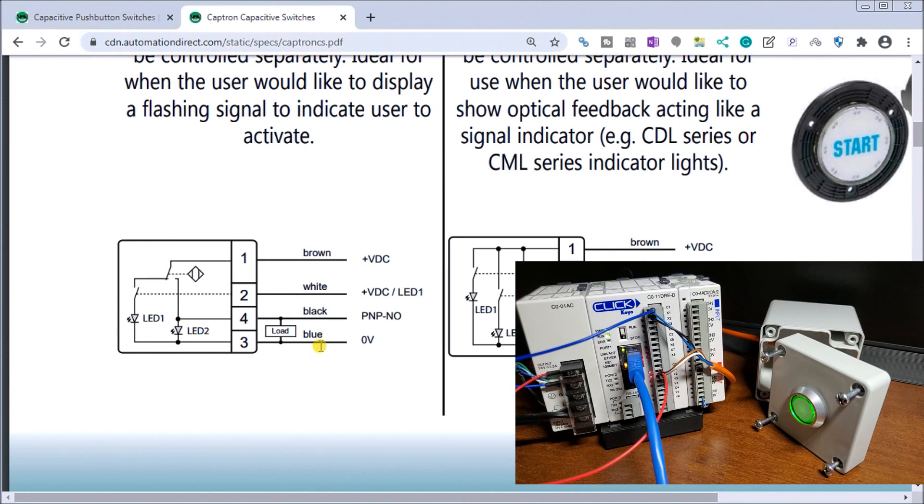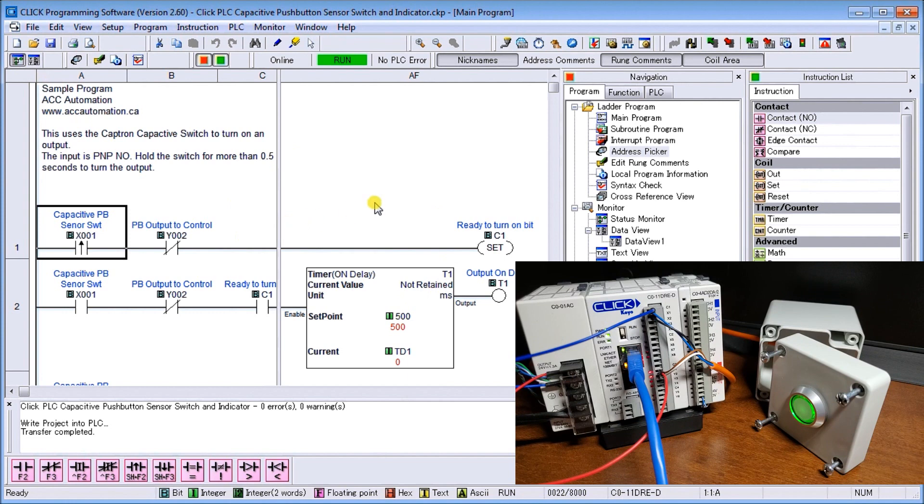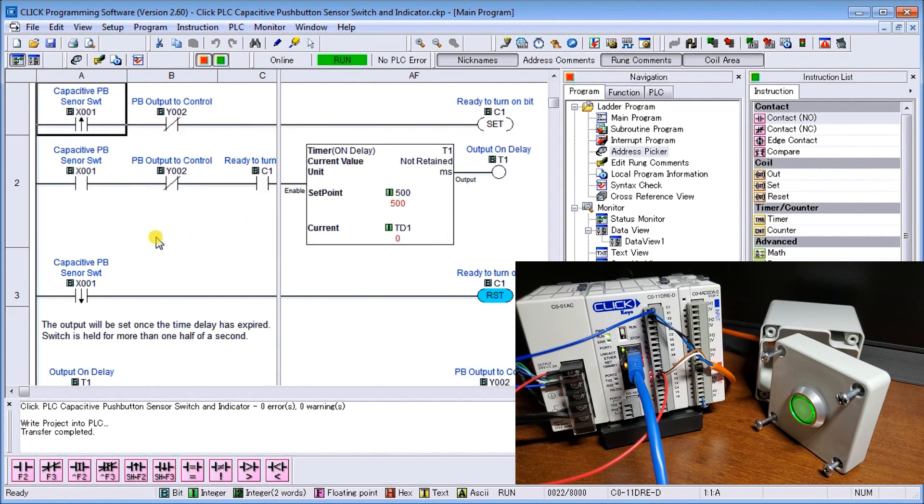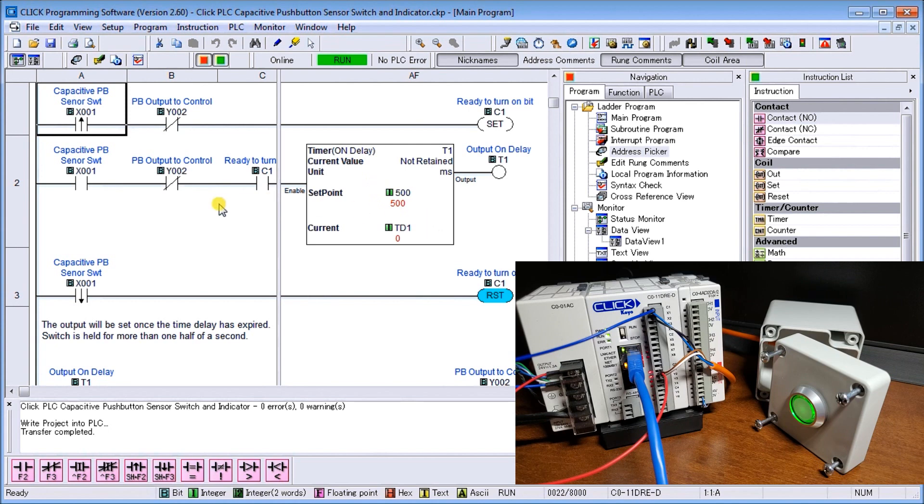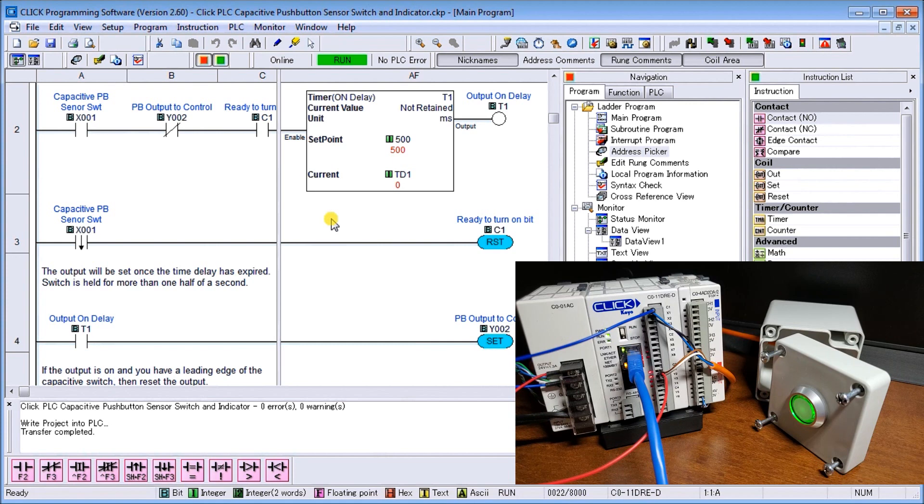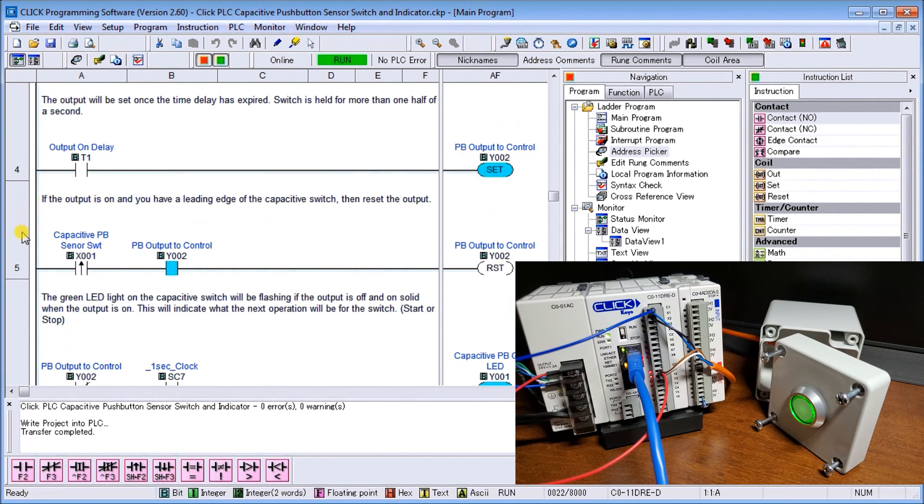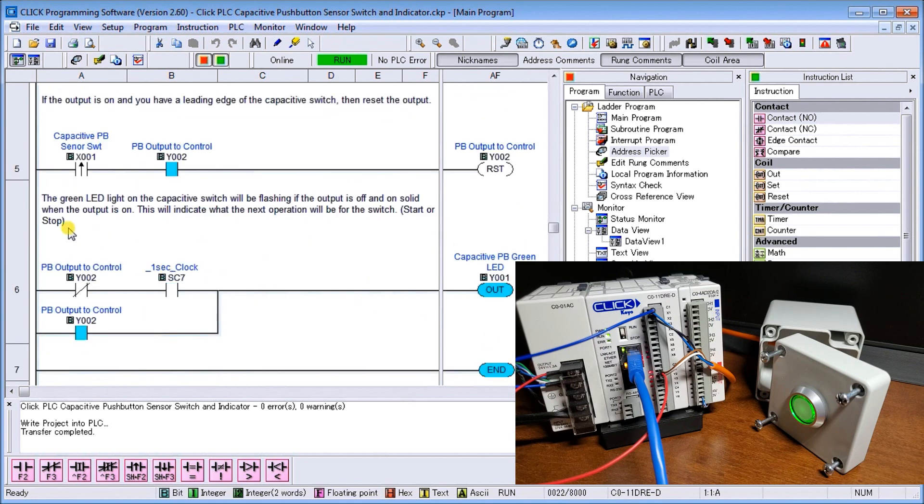So if I call up the Click software and you can see here that we are monitoring, and what I've done is actually create it so that I would need the sensor activated for more than half a second or 500 milliseconds before the actual sensor will switch. So the timer times out and then I actually turn on my output bit which is Y2. Now when Y2 is on, which it is right now, then anytime I get an input on the leading edge of my input signal it will turn off that Y2 signal. Then when Y2 is off, then what we do is we blink Y1. When Y2 is on, then we keep Y1 on, so that is our green LED light.